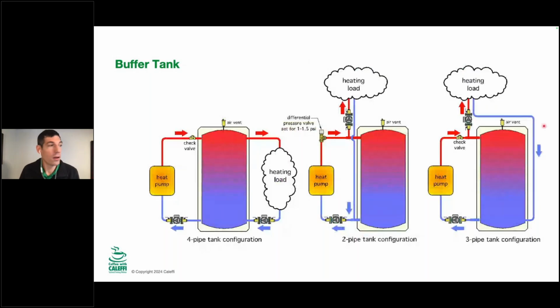How do we pipe these things? So the typical one that we use in the rest of the slides is as if it were a hydro separator. This can be a good fit in a lot of different cases. One of the things that I mentioned briefly from a temperature perspective that can be an impact to choose a 4-pipe configuration with a buffer tank is that if this is a 140-degree supply and we need 140 degrees for our heat loss for whatever our terminal units are out in the building, we might not have that. We might have 140 here and 135 by the time it mixes with the return based on whatever the flow rates are going out to the building. So if that's the case, a 4-pipe tank configuration does lead to mixing in this vessel. So we're going to shave a couple degrees, maybe only a couple degrees off of the maximum outlet temperature here.